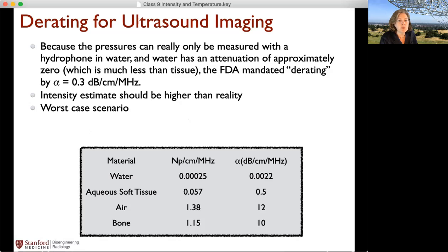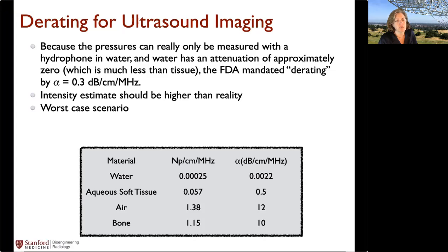And of course, this attenuation number is much smaller than it is for soft tissue. You can see the table down here. That's because they really want those estimates to be a worst case scenario, so that the intensity estimate should be higher than reality, and so that the actual intensity is less than their estimate, and it's going to be safer.